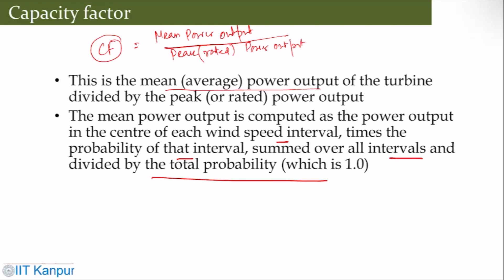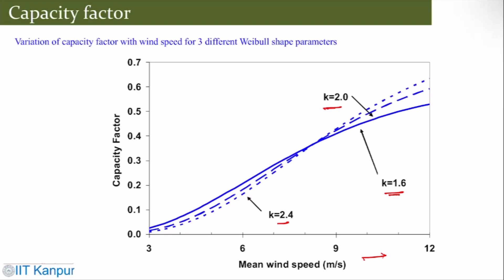What you can look at here is the variation of the capacity factor with wind speed for three different Weibull shape parameters, varying over kappa. One can see how the capacity factor varies over a different range of wind speed. This gives you an idea of how the capacity factor changes, and also one can see the capacity factor variation for different kinds of wind turbines. This N90 has a 90 meter rotor blade diameter. This is 80 meter. This is 100 meter. And their power output is pretty much in a similar range, 2.3 to 2.5. But you can see how the capacity factor varies with the different mean speed.